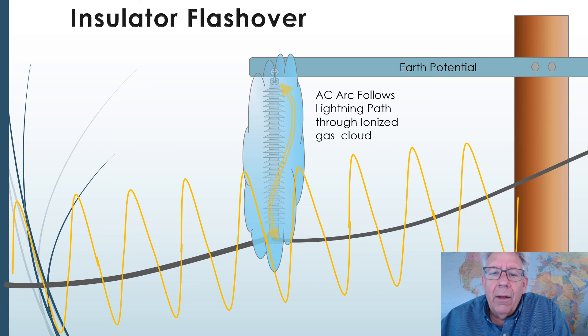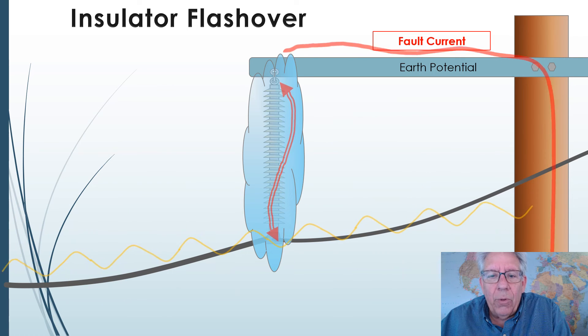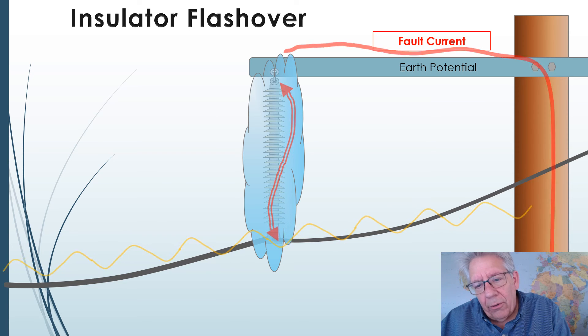So this AC arc then flashes over and we have fault current that begins to flow from the power system across the insulator, across the cross arm and down to earth.